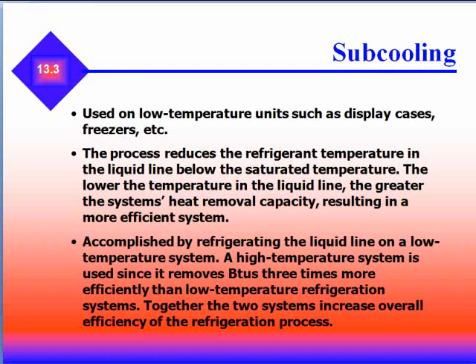Subcooling is used on low temperature units such as display cases or freezers. The process reduces refrigerant temperatures in the liquid line below the saturation temperature. The lower the temperature in the liquid line, the greater the system's heat removal capacity, resulting in a more efficient system. Subcooling is accomplished by refrigerating the liquid line in a low temperature system using a high temperature system, since it removes BTUs three times more efficiently than low temperature refrigeration systems.